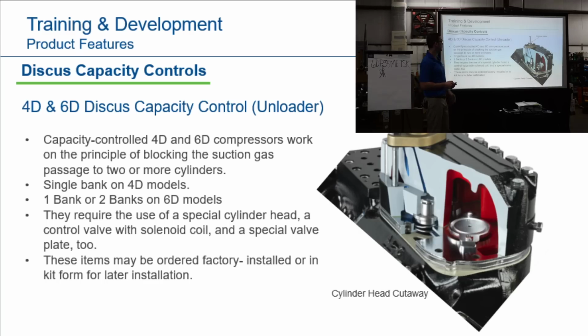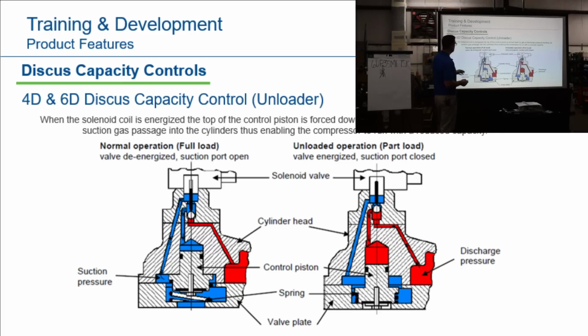Discus capacity controls. I'm going to go through this a little bit. 4D and 6D, we talked about it already. It's for capacity control. So the head will load and unload. Right? So the 4D, when you don't have the solenoid energized, you're at full capacity. When you energize that, you're at 50% capacity. Does that make sense? Okay. And this is normal operation, fully loaded, de-energized. When the valve is energized, the suction port closes. So that's how you're getting your capacity control.